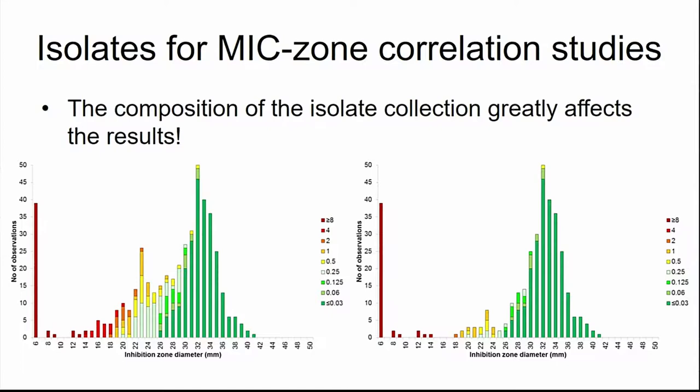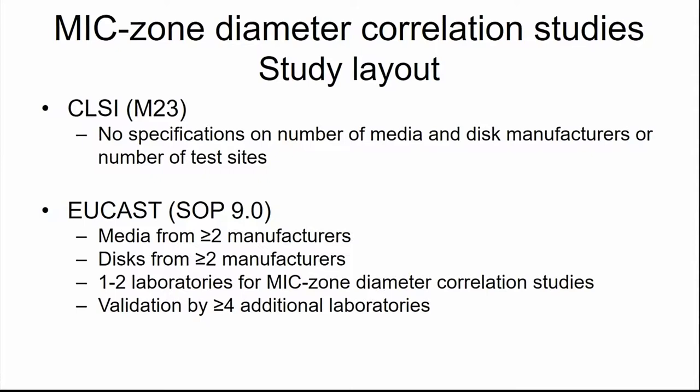How these studies are set up differs between CLSI and EUCAST. Currently, CLSI guidelines do not specify the number of media or disc manufacturers or testing sites. EUCAST specifies media from at least two manufacturers, discs from at least two manufacturers, and performs the basic MIC-zone diameter correlation work at one or two skilled laboratories, followed by a validation study involving network laboratories. It is extremely important to demonstrate that the method is robust across materials from different manufacturers.